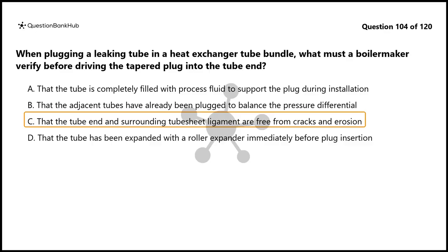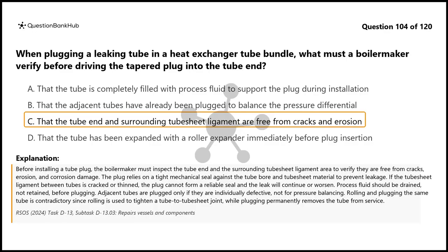The correct answer is C. Before installing a tube plug, the Boilermaker must inspect the tube end and the surrounding tube sheet ligament area to verify they are free from cracks, erosion, and corrosion damage. The plug relies on a tight mechanical seal against the tube bore and tube sheet material to prevent leakage. If the tube sheet ligament between tubes is cracked or thinned, the plug cannot form a reliable seal and the leak will continue or worsen.